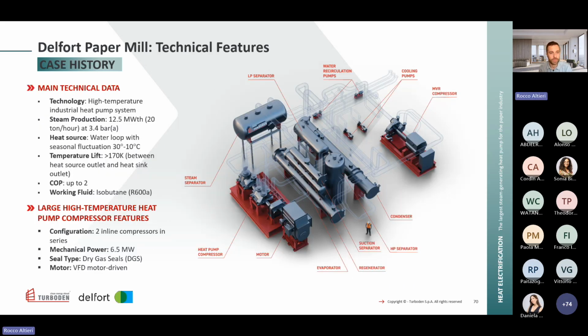Talking about some technical features of this system, the steam production is up to 20 tons per hour of steam. So the equivalent thermal power supplied is 12.5 megawatt at 3.4 bar absolute, as I said before. And 170 degrees. So the steam conditions are superheated.